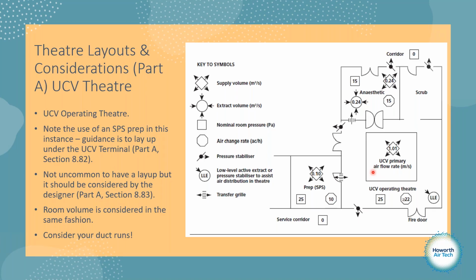When we have a layup prep room, there's enough air change rate in there and enough door protection in that room, and the air change rate will be really high, so you can open the pack, check everything's in there, and then be ready for the next procedure to come through. Because this is HEPA filtered, the Royal College of Orthopaedic Surgeons say that should happen in here, and that's in HTM.